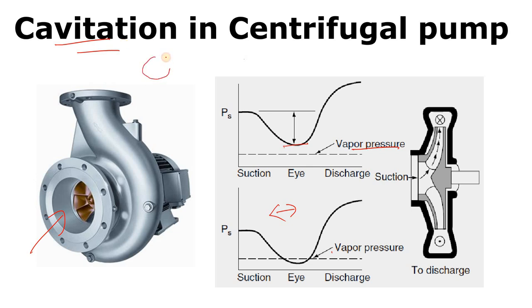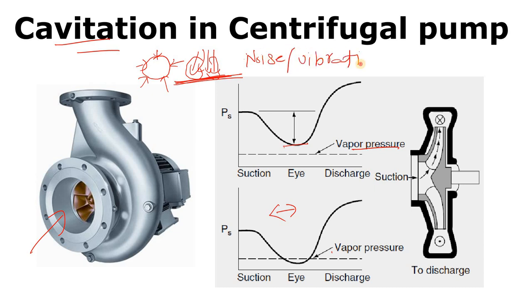As the vapor bubbles form and then collapse, liquid fills or replaces that space. The velocity of the liquid replacing that space is very high, so it strikes at the surface of the pump. As this happens frequently, there is noise and vibration at that time. If there is noise coming from the centrifugal pump, you can say that cavitation is at its peak — meaning there is extreme cavitation occurring.